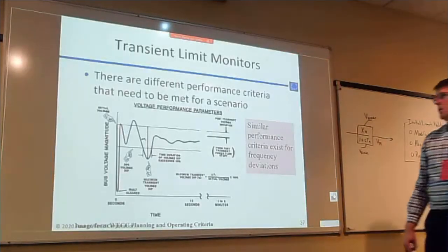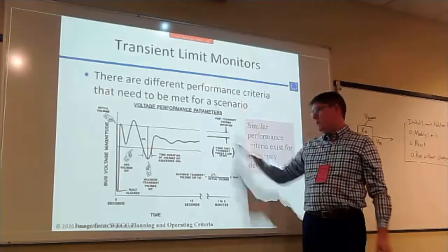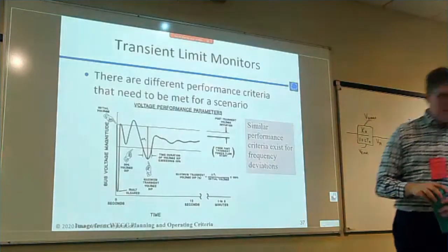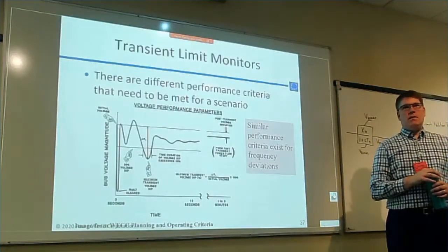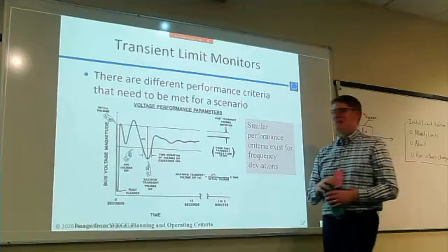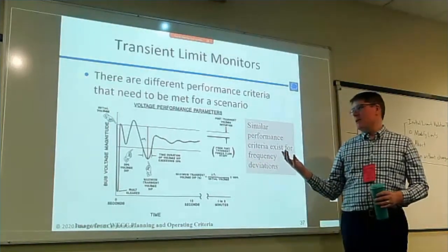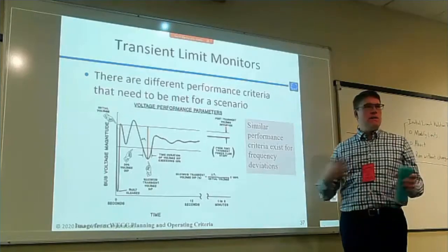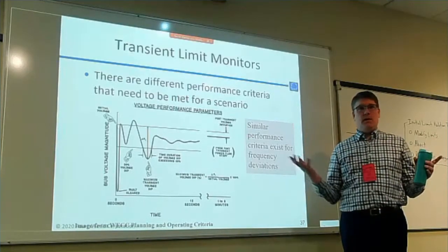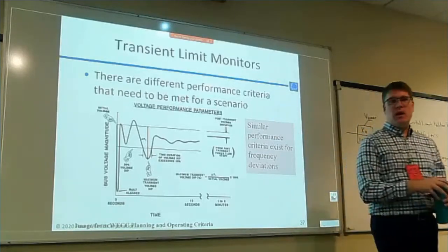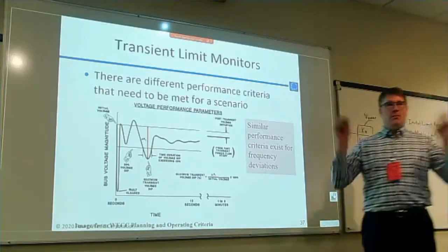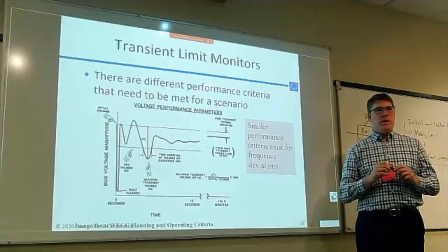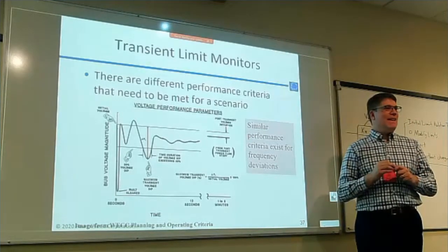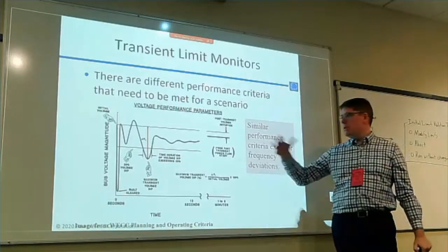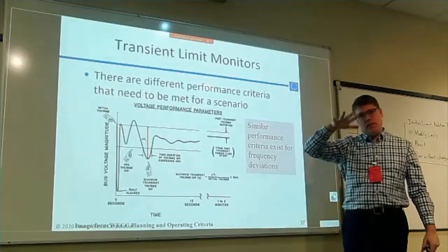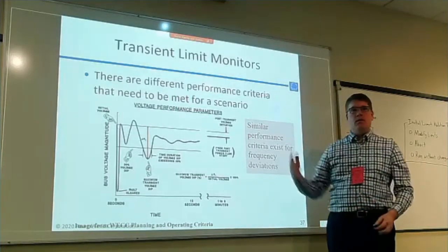All right, this then goes to tomorrow I'll talk about transient limit monitors and the WECC finger diagram. You guys have been around long enough to hear that term. It came about in WECC first because you guys actually started modeling induction motors after the 1996 blackout. You had what you called the interim load model, which was around for about 20 years. But it was an improvement because it was including some of this behavior that when a fault happened, the voltage would drop and the system doesn't recover right away.